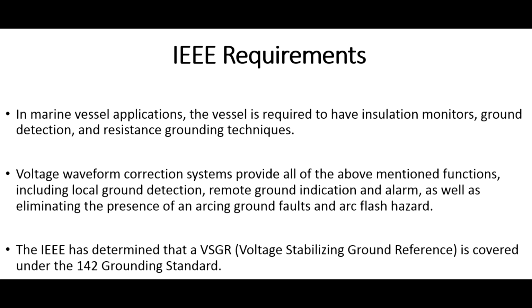A little bit about standards. The IEEE controls, regulates, and dictates to the marine industry, Coast Guard, American Bureau of Shipping, and so on, what the power systems have to be and what they have to include. They have to include insulation monitors to keep track of whether there is a ground potential forming, and then when it happens, ground detection to detect that it's physically there, and something called resistance grounding to limit the amount of current if in fact the system shorts to ground. The voltage waveform correction systems provide all of these functions. In addition to that, you have local ground detection, remote ground detection, indication and alarm, as well as eliminating the presence of arcing ground faults and arc flash. So it doesn't only monitor the events, it prevents them from happening.